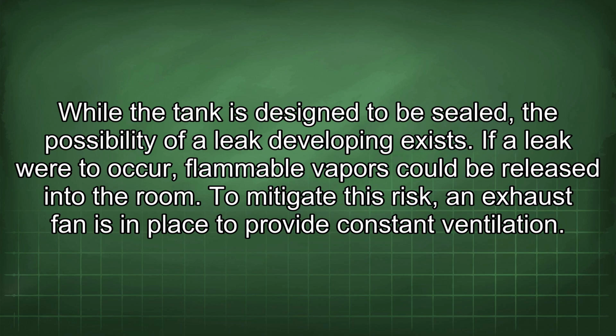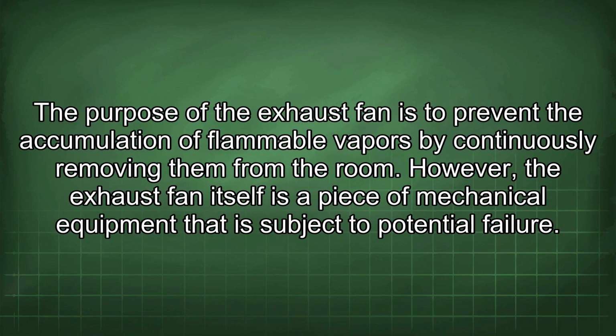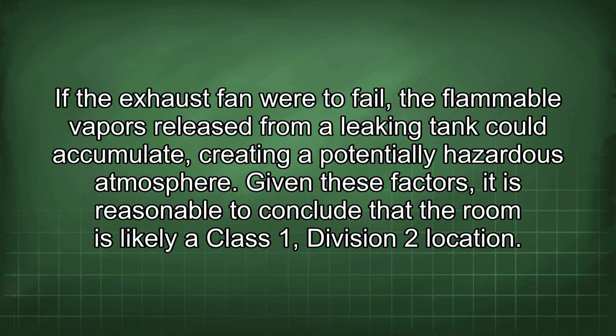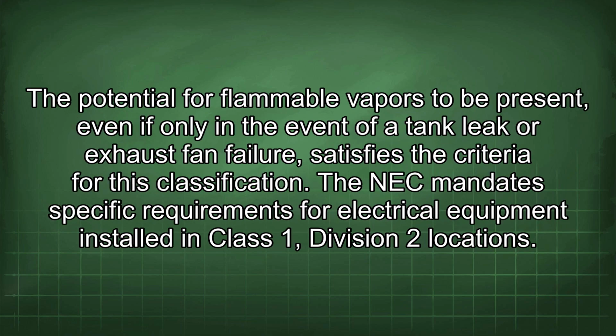To mitigate this risk, an exhaust fan is in place to provide constant ventilation. The purpose of the exhaust fan is to prevent the accumulation of flammable vapors by continuously removing them from the room. However, the exhaust fan itself is a piece of mechanical equipment that is subject to potential failure. If the exhaust fan were to fail, the flammable vapors released from a leaking tank could accumulate, creating a potentially hazardous atmosphere. Given these factors, it is reasonable to conclude that the room is likely a Class 1, Division 2 location. The potential for flammable vapors to be present, even if only in the event of a tank leak or exhaust fan failure, satisfies the criteria for this classification.